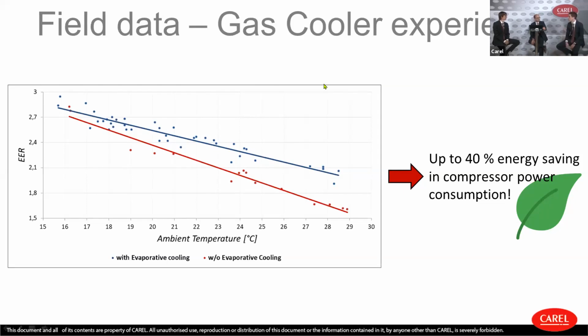There's a slide I always display because it's very interesting: the chill booster was born as a booster, a way to overcome the peaks during the hot season, let's say the end of July, what in the past someone was using just by pouring water over the condenser. But here it's a completely different approach, especially for process cooling, which has in common with this experience that it's for refrigeration, cooling all year long. So it's a different way of seeing that: not to overcome the peak, but to take advantage of the seasonal efficiency.